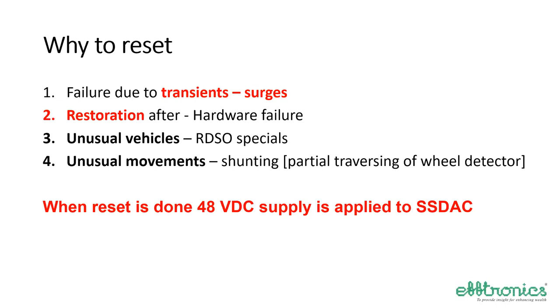Unusual movements, that is shunting. While shunting, let us say instead of A and B channels, only the A channel is touched and the vehicle comes back. Then what is to be done? Shall it be considered as a count or not? These are the unusual movements. In some cases there is, I think, a concession at present. If a single wheel sensor is traversed up to two times, I think it won't fail. If it is more than two times, it goes into a failure mode. What happens is, when reset is done, 48 volt DC supply is applied to the SSDAC.